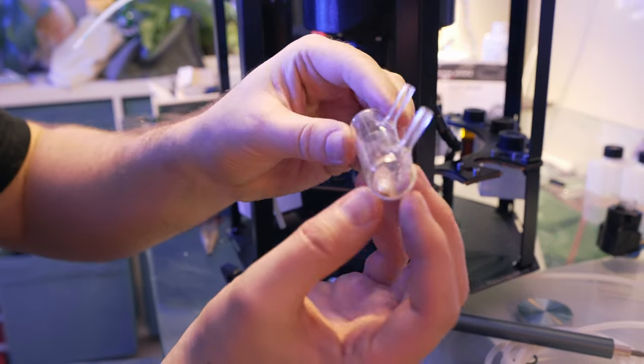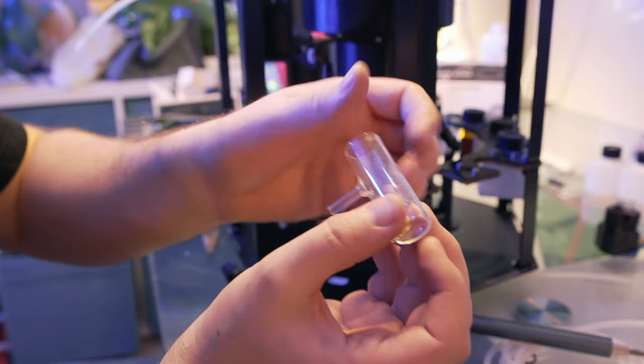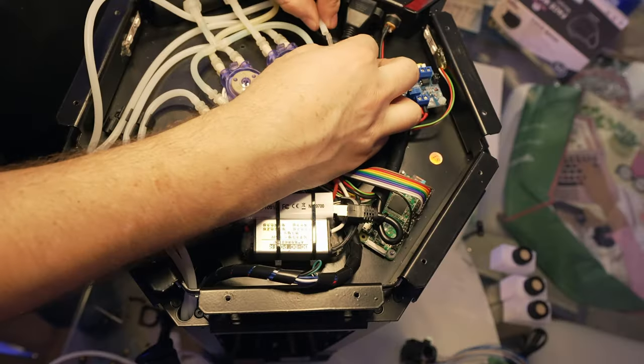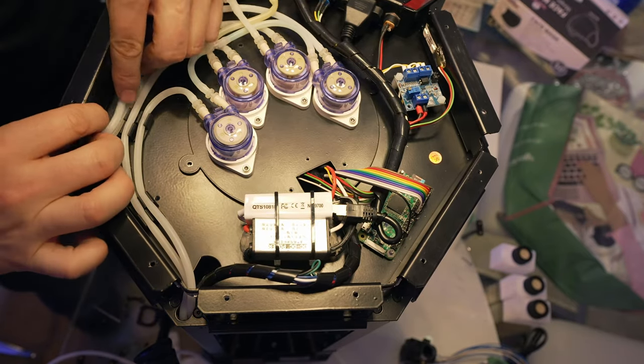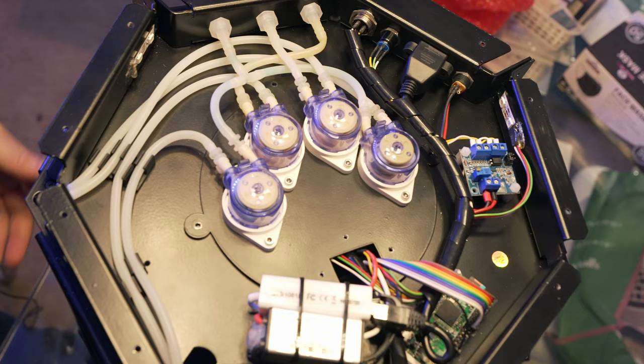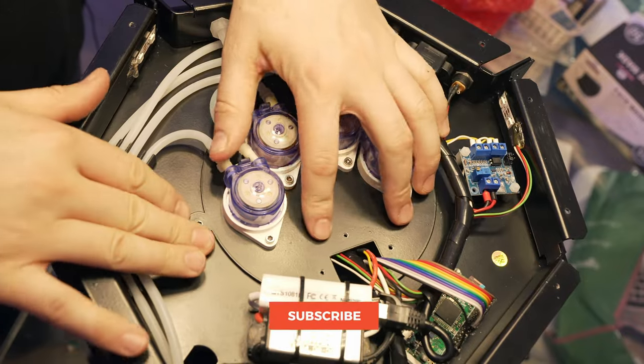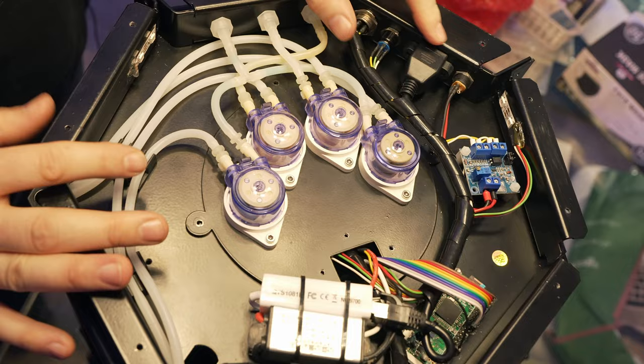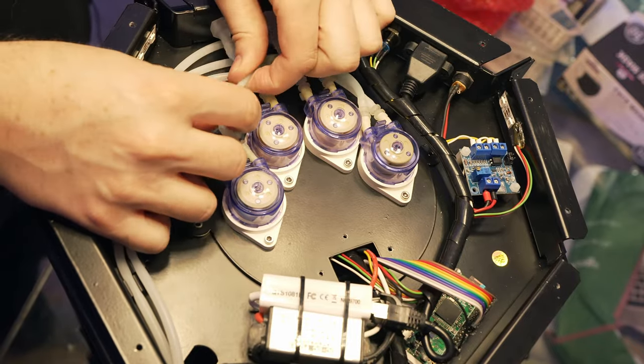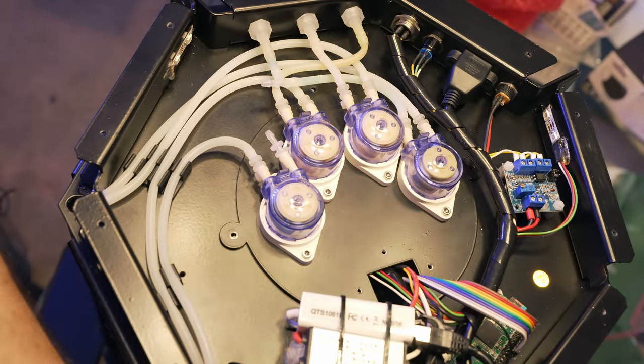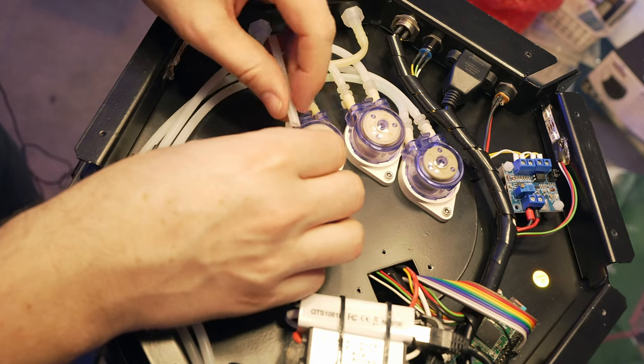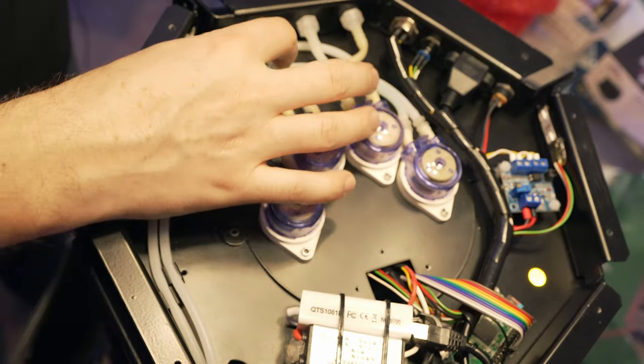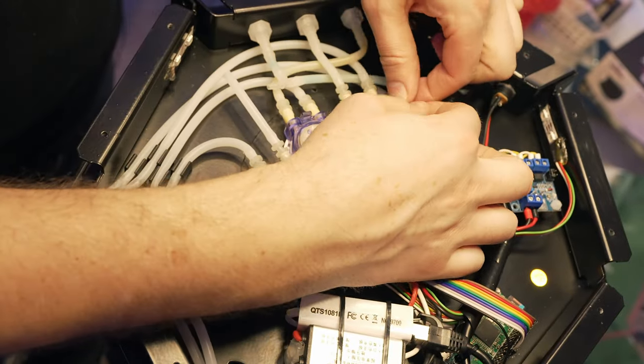And since we're in maintenance mode, if I look inside, there's a little bit of coloration, a few things. So I'm just going to give this a quick rinse with the RODI and wipe it out with a paper towel. Much better. Makes it pretty easy if they have the same size tubing for basically everything. Now, of course, the only thing really left is to put all your screws and all your parts back together. This is a little bit of the bonus content, but I think I'm just going to replace that couple little bits of tubing that's discolored. Sometimes some machines are calibrated based on the length of the tubing. So just a little bit preventative if you keep it basically the same thing. If it's a smidge off, it probably doesn't matter. And looking at this, this is the waste line, so this one doesn't really matter on that front.